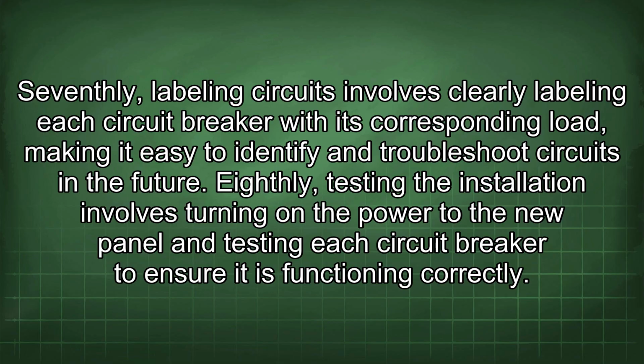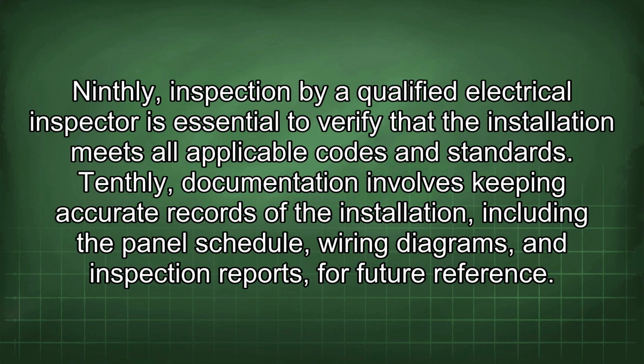Seventhly, labeling circuits involves clearly labeling each circuit breaker with its corresponding load, making it easy to identify and troubleshoot circuits in the future. Eighthly, testing the installation involves turning on the power to the new panel and testing each circuit breaker to ensure it is functioning correctly. Ninthly, inspection by a qualified electrical inspector is essential to verify that the installation meets all applicable codes and standards. Tenthly, documentation involves keeping accurate records of the installation, including the panel schedule, wiring diagrams, and inspection reports for future reference.